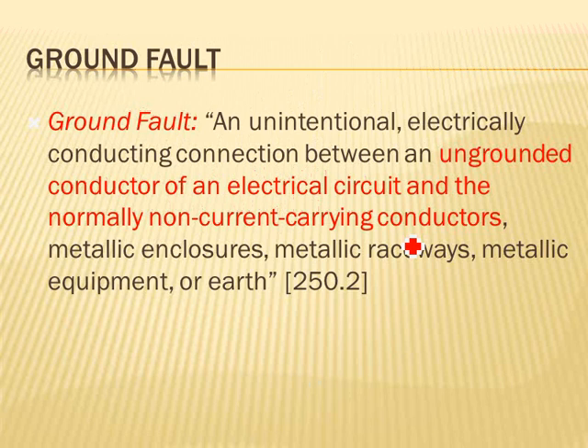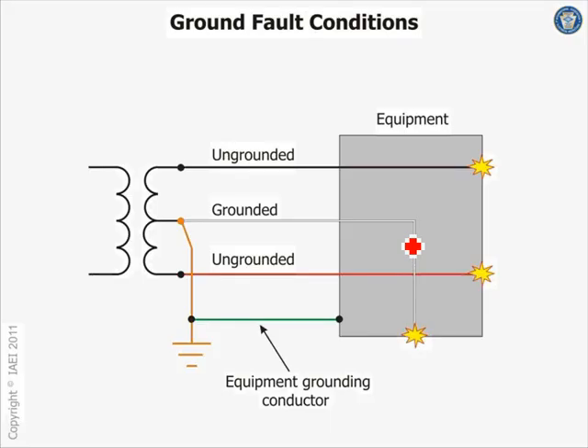A ground fault is between the ungrounded conductor of an electrical system and a non-current-carrying conductor. For example, if you have any phase to the frame, that will be a ground fault. Phase to the frame, that's your ground fault. Any questions about ground fault? Every time you have a hot to the ground, the frame, the boxes, that's your ground fault. Any hot to hot or hot to neutral is a short circuit. Who cares? If you have ground fault detection here, it will be looking at the current that's coming on the ground, the current coming back into the ground. It would not see phase to phase or phase to neutral.